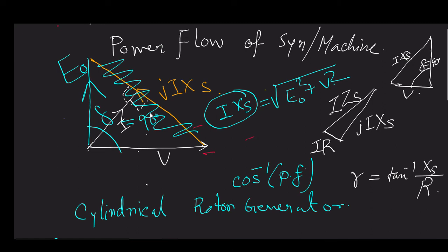So even if you are considering leading, lagging, still the value of I that you need to circulate through your capacitive load is so high, because XS you cannot change. For a given machine, XS is fixed, right? And if it is an economically designed machine, then the XS should be kept within a band. So you need to circulate a huge amount of current I, and in reality that is in no way possible. So that limits us to keep it within 40, because of stability and all other considerations.